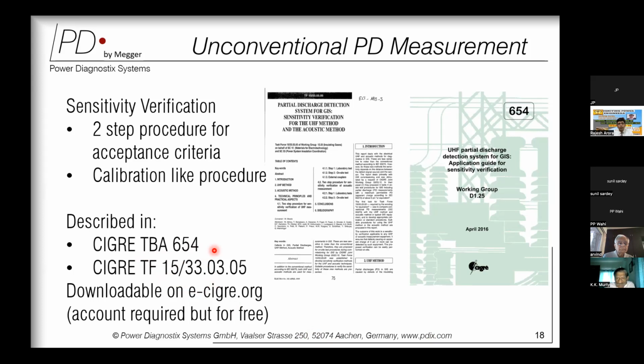Now, these are the two documents which talk about the sensor placement and the measurement which we do with the sensor. The procedure is called sensitivity verification. This sensitivity verification is a two-step procedure, and it is set up as an acceptance criterion for accepting any GIS. It is almost like a calibration-like procedure.